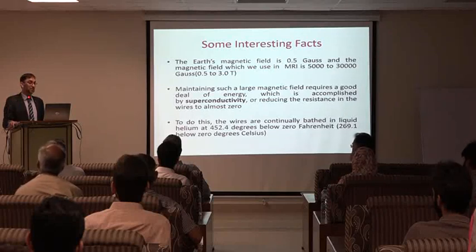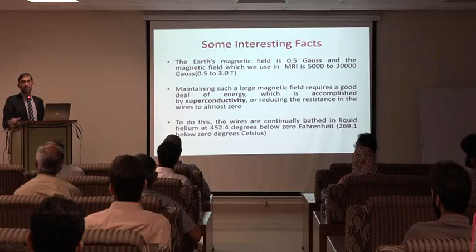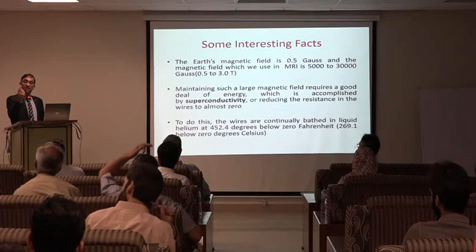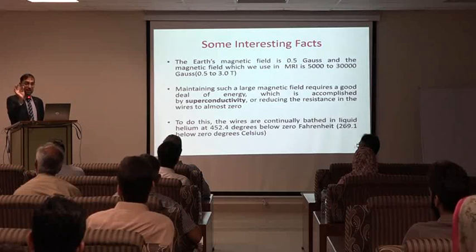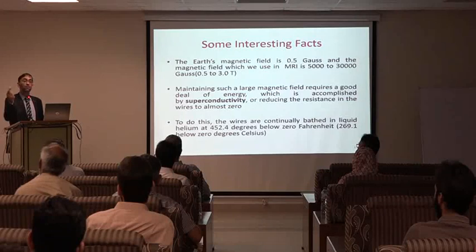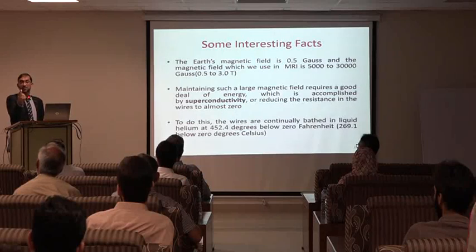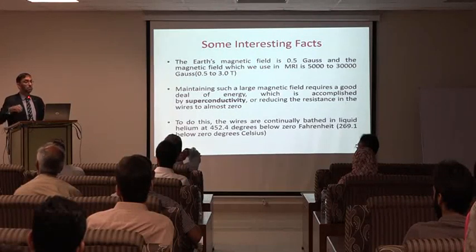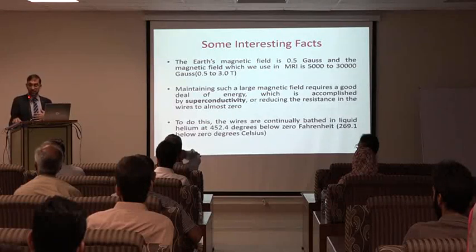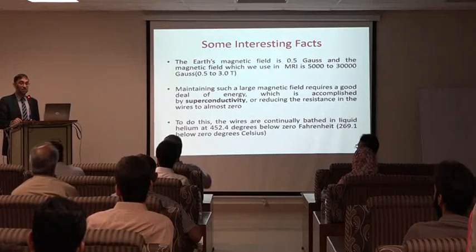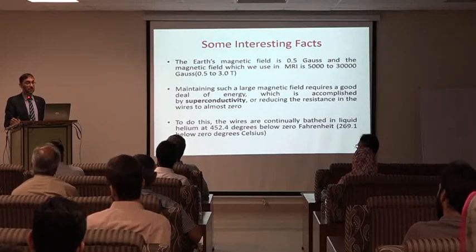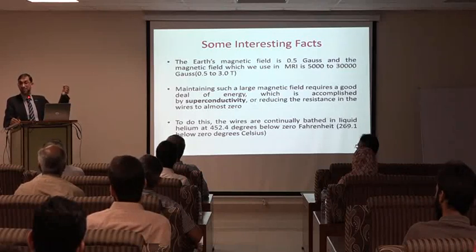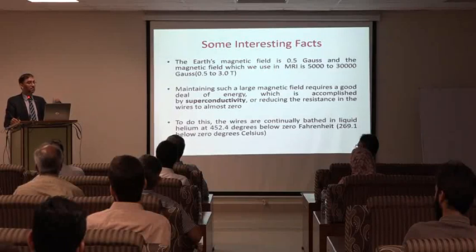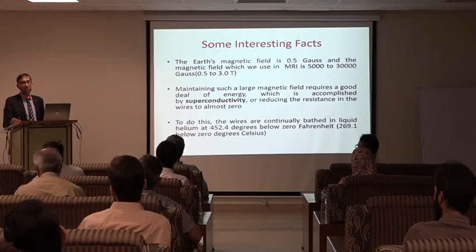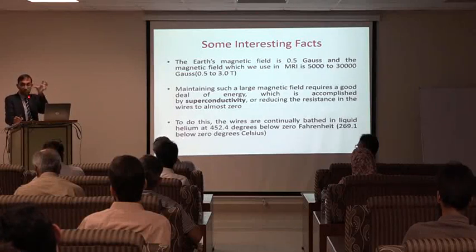Why? To maintain superconductivity. Because sometimes a phenomenon happens when even a slight part of that wire is not fully bathed in helium. What will happen? It will start giving out heat, and that heat will boil all the helium, and there'll be a blast. And that is known as quench mechanism. That's a safety mechanism at almost every scanning facility. But one of the main operational costs of MRI scanner is you have to continuously refill helium, and it's quite a few hundred liters of helium we are talking, right? Which has to go into that core where the wires are there.